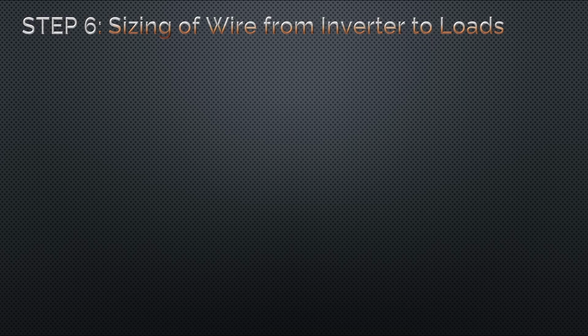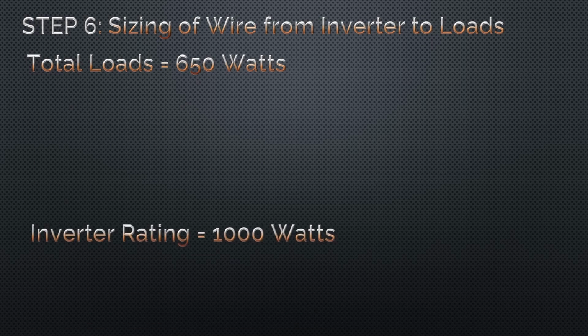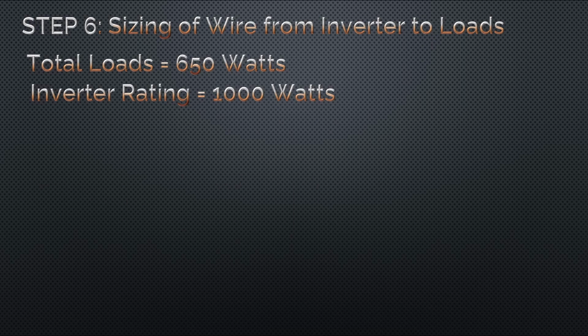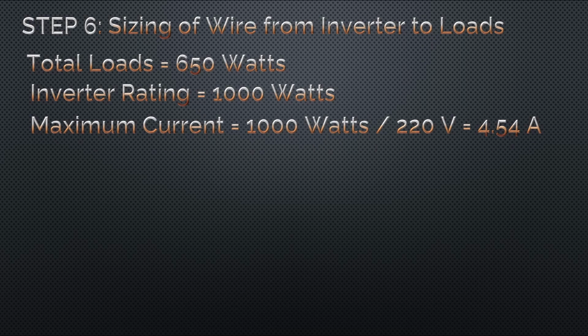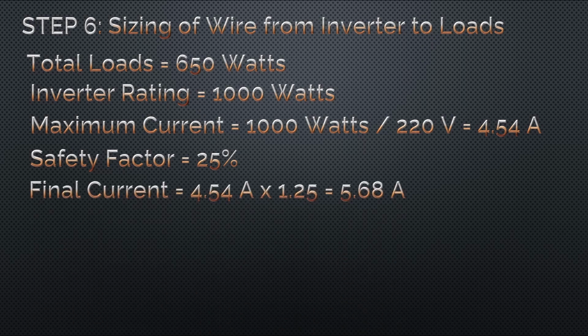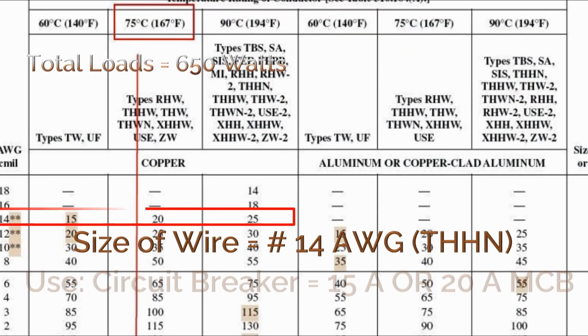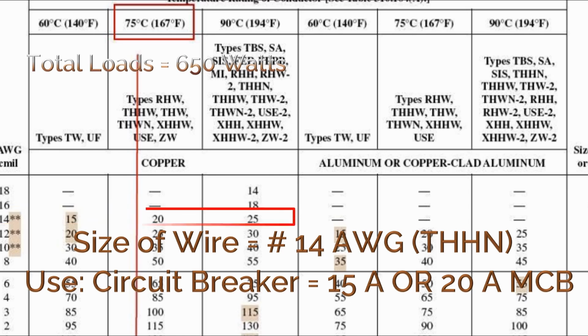To size the feeder wire from inverter to loads, you have to consider the total wattage of the loads, but sometimes you must consider future expansion. So you will use instead the inverter capacity. The maximum current using the inverter capacity is 4.54 amperes. Also, you must consider applying the safety factor for continuous loads. So the final current will be 5.68 amperes. If we look in the ampacity table, we will use number 14 AWG THHN. Also, the AC circuit breaker to be used is a 15 ampere or 20 ampere rating miniature circuit breaker.